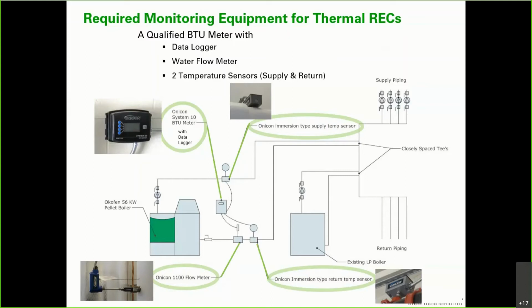So the BTU meter registers that. It has to record this about once an hour and give you all this background data. But in the end, someone approves that, and that tells you how much heat this boiler system actually used, which converts directly into the thermal RECs that you've created. There are these electronic sensors here, and then the last thing is the flow meter. You can't just look at temperature in, temperature out. You've got to find out what volume of flow there was at that time as well, and that tells you exactly what your BTU gain was.